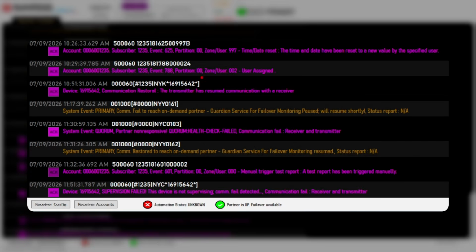You see, the Sur-Gard receivers were the first IP receivers to really take off, and they set the standard for what IP receiver-generated signals would be. And they chose to use the SIA format for these signals. For the sake of consistency, other manufacturers, including NAPCO, continued with this standard, which is why the NAPCO VIP receiver also generates YCs and YKs for poll fails and restores.